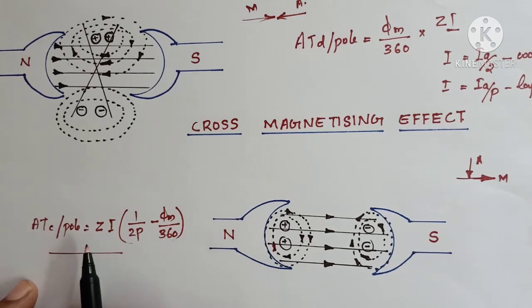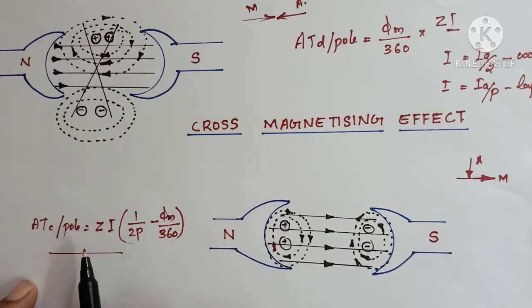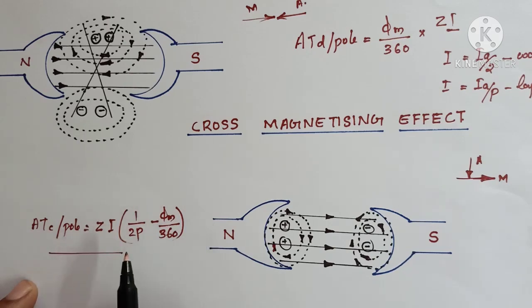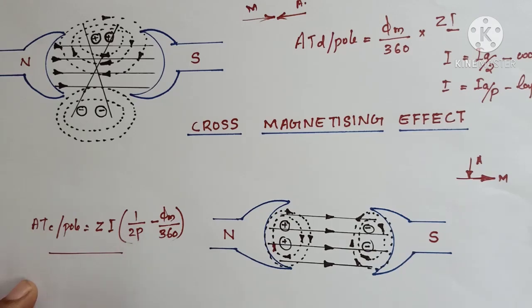The cross-magnetizing effect can be calculated using this equation. Cross-magnetizing ampere turns per pole equals Z × I × [(1/2P) − (φm/360)]. All the terms here are familiar from before.